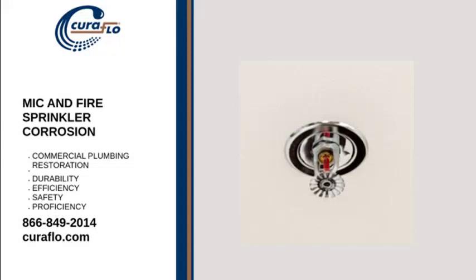Epoxy pipe repair is another solution that is very effective at treating MIC by eliminating the contact between the microbes and the wall surface of the pipes. Analyzing the frequency of alarm and drain testing may reduce the non-biological and biological corrosion types that could grow when fire protection systems are drained and refilled.